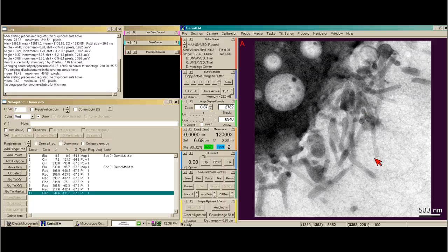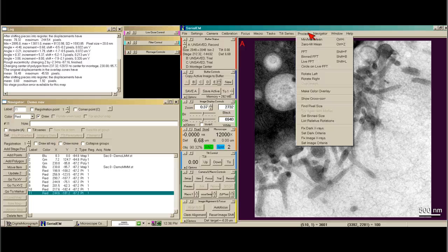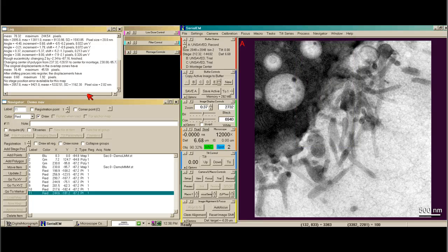Here's my final image. I'm going to look at the counts value here — on our camera, I want my counts to be around 8,500. To see what the average counts between the black and white are, I can go to Process > Min, Max, Mean. In here it tells me my average counts were only 5,300, which isn't quite bright enough.